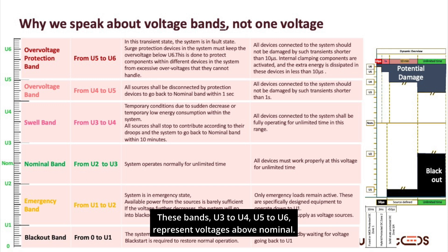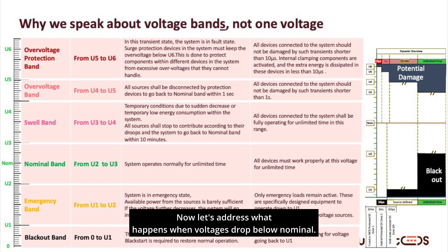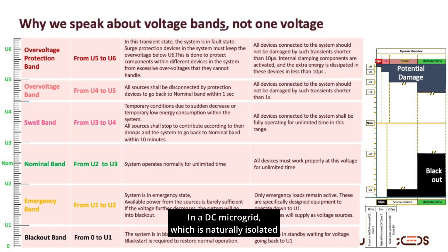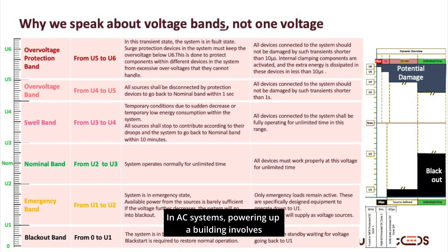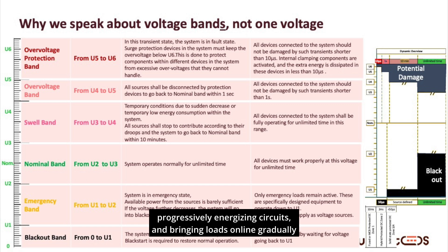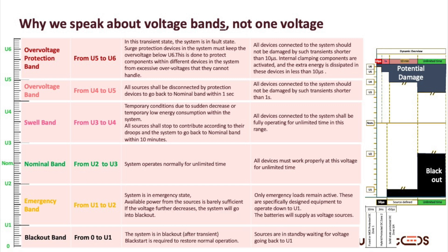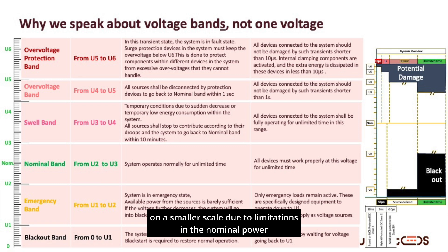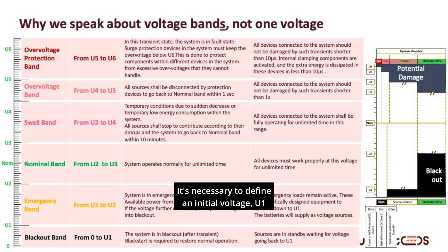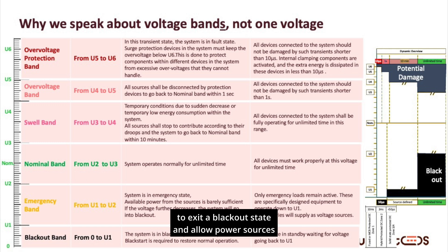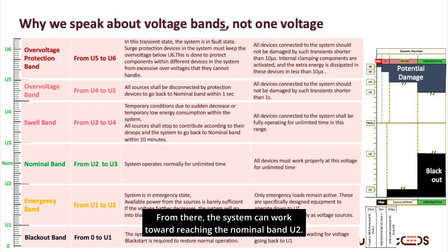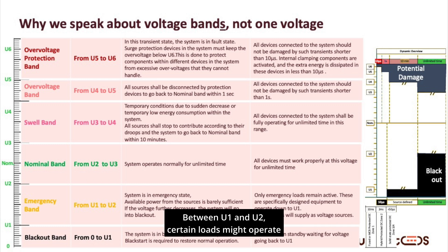These bands — U3 to U4 and U5 to U6 — represent voltages above nominal. Now let's address what happens when voltages drop below nominal. In a DC microgrid, which is naturally isolated from the public grid by an AC-DC converter, startup poses unique challenges. In AC systems, powering up a building involves carefully managed steps: magnetizing the transformer, progressively energizing circuits, and bringing loads online gradually to avoid tripping protections due to high inrush currents. DC systems require a similar approach. It's necessary to define an initial voltage, U1, to exit a blackout state and allow power sources to begin contributing. From there, the system can work toward reaching the nominal band, U2 to U3. Between U1 and U2, certain loads might operate in emergency mode — for instance, safety lighting or fire protection systems.